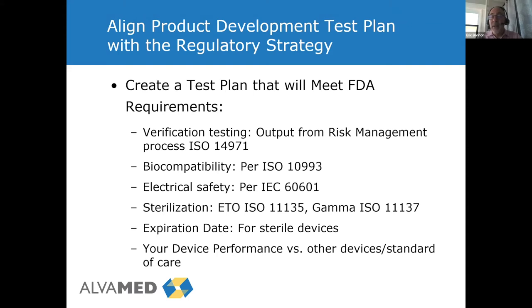And not come up with a non-approval or, for the 510K process, a non-substantial letter. So these are some of the things to think about. Verification testing, right? This is output from your risk management process, your 14971. You put together a matrix of inputs and outputs. You identify the testing you would generally use: biocompatibility per 10993, electrical safety as an example, sterilization, whether it's ETO or gamma.